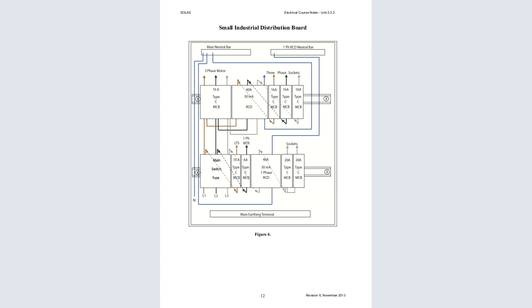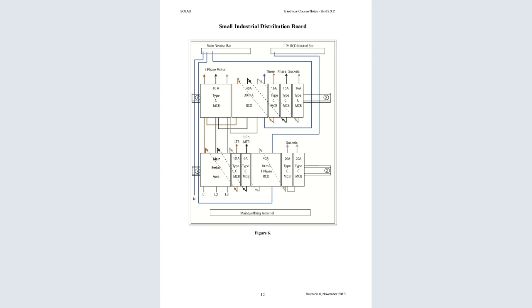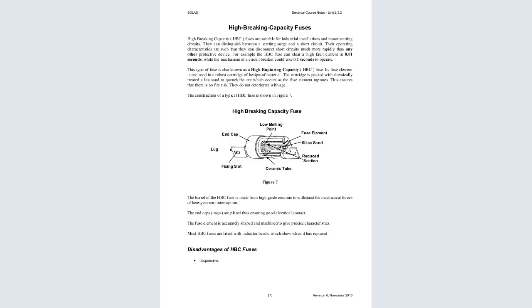The one that is used for the switching, the MCB, is fed from the main neutral bar. You can see it here. And then you can see the three-phase motor where it is being loaded. The main switch is here. And these are the other breakers that are tapped. You can see how the other breakers are, and the neutral is being fed to all these circuit breakers. You can see the other circuit breakers to the sockets, and the three phase is here. The sockets, you can supply as many sockets as you want. And you can see the main switch is there. This is the supply from the pole. And this is the earthing bus bar that is there.